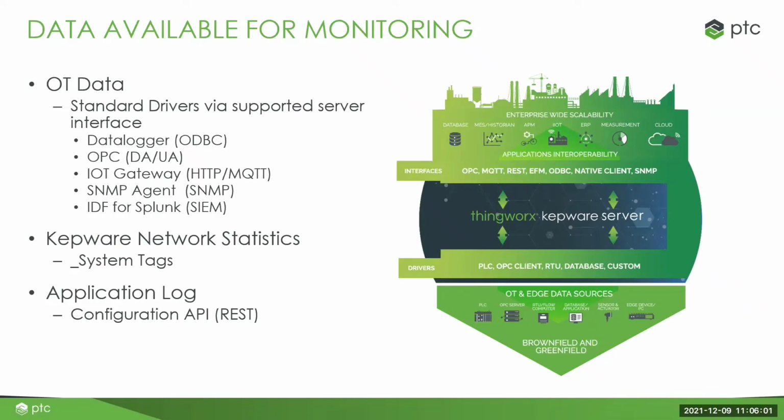For example, you can connect using the SNMP agents to the managed switches and things like that for you to look at the MIB file and see how the network is like. If you're using UPS and you want to monitor your backup power, you can use the SNMP driver as well. If you need to send data out to somewhere else, you can use the SNMP agent plugin. For example, you have an NMS and you want to send it out, you can also use Kepware to do it, to bridge the OT data into the SNMP or IT side of things.